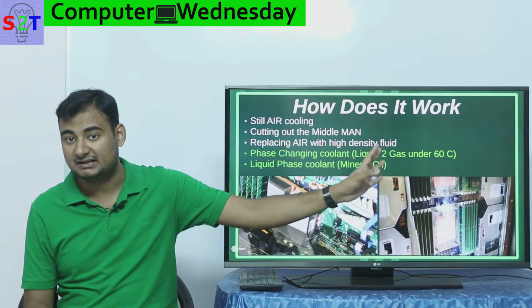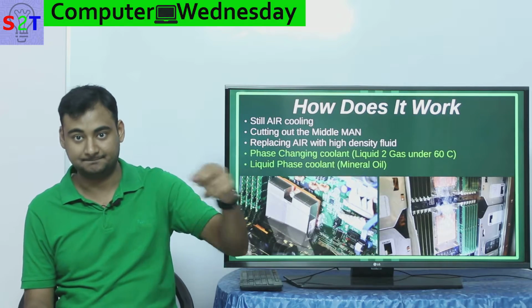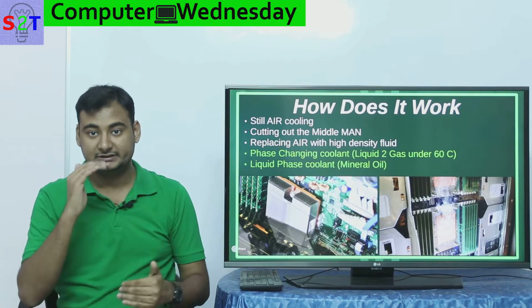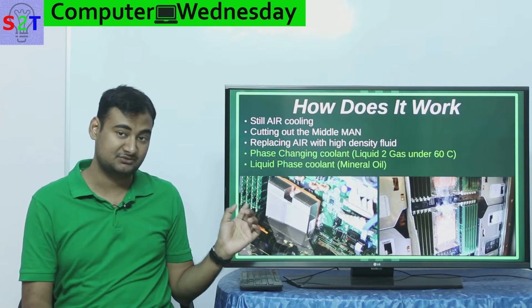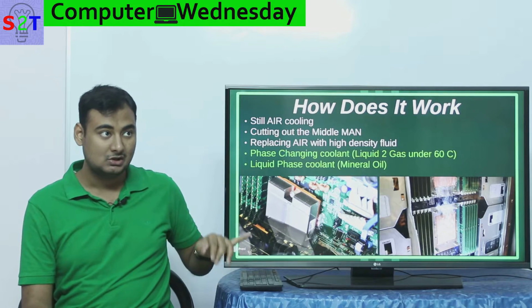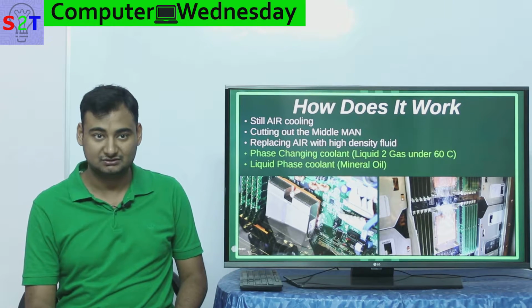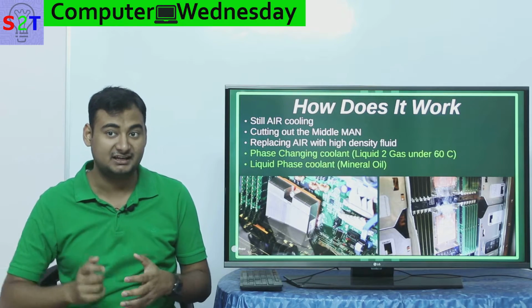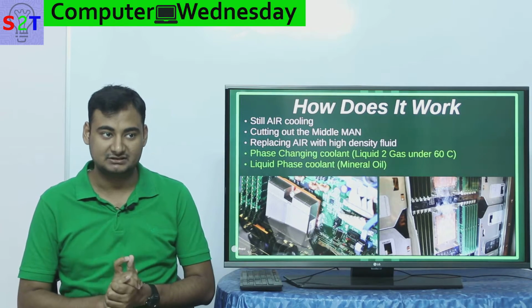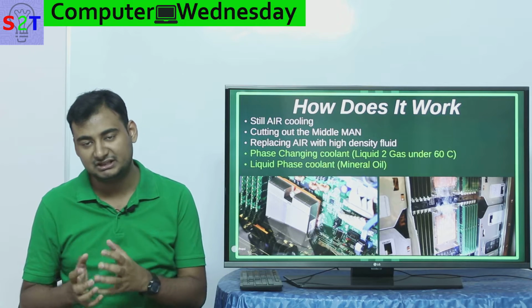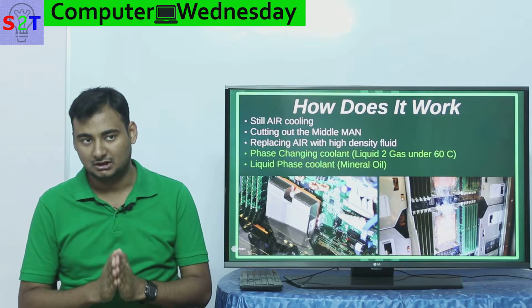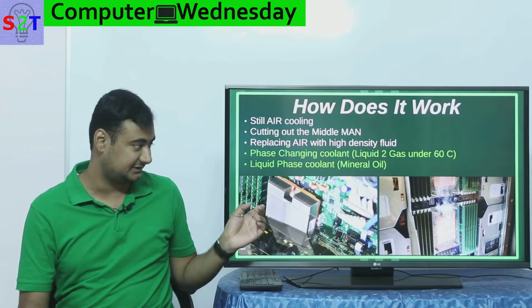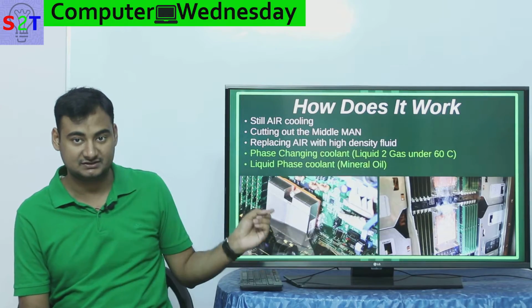The benefit of this architecture is that it does not require a pumping mechanism, because the fluid keeps moving on its own. With oil submersion, you need seriously strong pumps, because even though oil has similar density to water, its higher viscosity means you'll need much more powerful fluid pumps for that setup. So this two-phase method does not require a pump, while the oil method does require pumps.